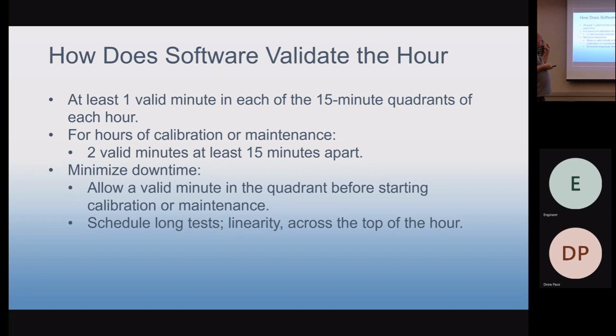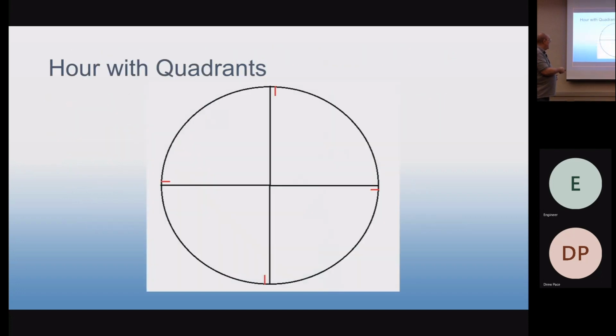And like I say, to minimize downtime, you need to pay attention to when you're doing maintenance or when you're starting a cal. If you want to do something with the system, you can always give yourself a little hedge if you wait a little after the top of the hour, or a little after, say, 16 minutes or 17 minutes into the hour, et cetera, et cetera. So your target is just a little bit after each quadrant. You're starting a maintenance period or starting a calibration, and what that did is that quadrant's already valid. So you can go ahead and burn the whole rest of the quadrant and then work your way into the next quadrant. And if your maintenance is done before you get to the end of that second quadrant, boom, you've got a valid hour even though you did maintenance.